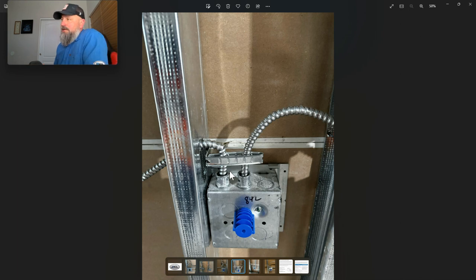And here we have a perfect example of what could happen. So this cable has broken, come undone. We've got exposed wires now. This is just well beyond the bending radius, and this cable just needs to be replaced now. It's been broken and needs to be replaced just to get it through this first punch out. I mean, service loop, go right out there.